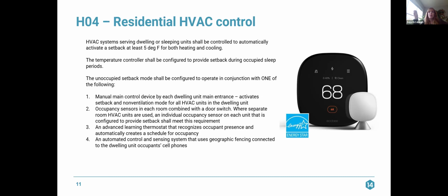The second option is to provide occupancy sensors in each room combined with the door switch. So where separate, and this is helpful for separate rooms, if you have like a PTAC in every room, it's a multi-room unit. Where separate room HVAC units are used, an individual occupancy sensor on each unit that is configured to provide setback shall meet this requirement.